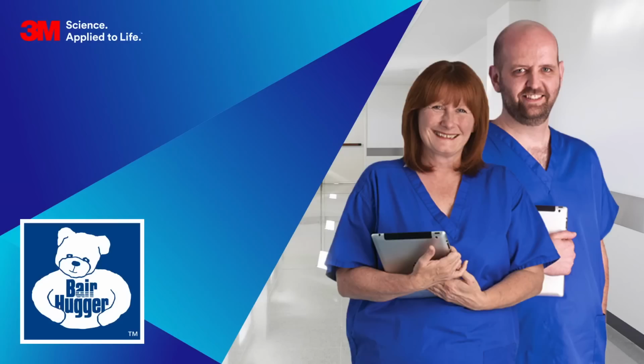Danny, regarding the 775 temperature management unit, how many airflow settings does the model have? Yeah, there are four settings. There are 32, 38 and 43 degrees. There's also an ambient setting, which allows you to circulate ambient temperature air around your patient. Okay, so the next question that we have is, when should the filter be changed on the 3M Bair Hugger temperature management unit? The filter should be changed every 500 hours of air blowing use, or every 12 months.